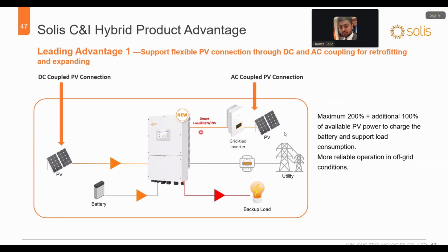But if you compare with other brands, they need to install a DC coupled system separately, because most BESS systems are AC coupled by default. Most of the BESS systems don't have DC coupling. But in Solis, we already have a built-in DC coupled system. All you have to do is install some PV here with the inverter, and together they can support all the requirements of the customer.